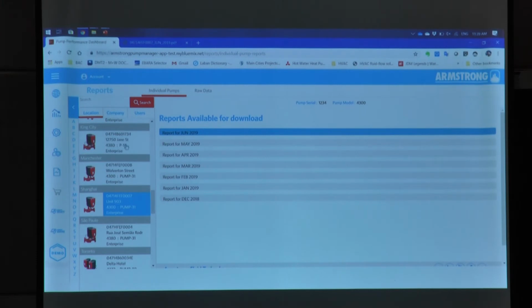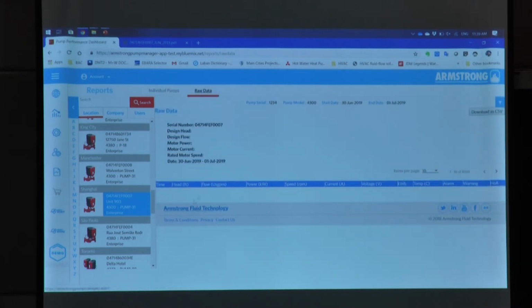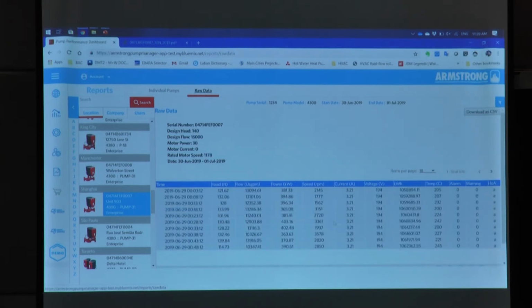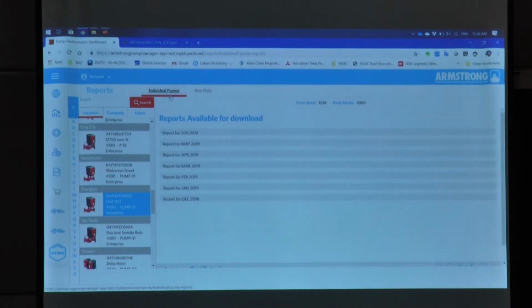So the report looks like this. It has the summaries of the pump, such as for the hourly flow profile, the monthly flow profile, and so on. And this shows the energy savings. Besides the individual pump reports, we have the raw data. It is also available on the pump manager. You can see all of the parameters, the head, the flow, power, and so on. So this is the demonstration for our pump managers.